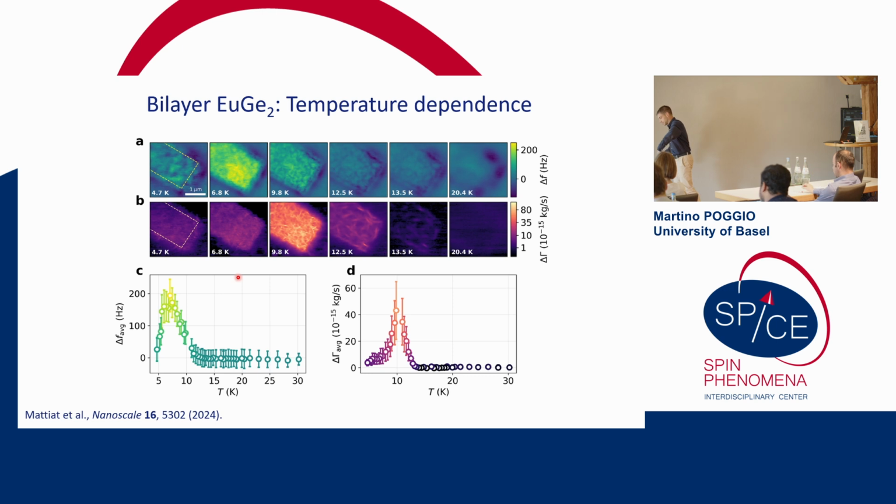You can imagine it's shaking over the sample like this, and you can measure, of course, the resonant frequency of that, so it's proportional, as I said, something like the gradient, and you can also measure the energy loss of the system. So the tip and the sample are interacting, and there can be, let's say, loss mechanisms that increase the mechanical dissipation of the cantilever. And that's exactly what you see here.